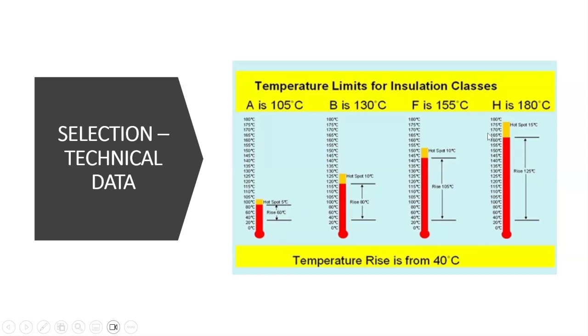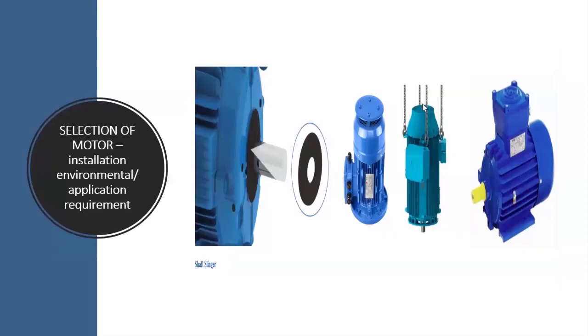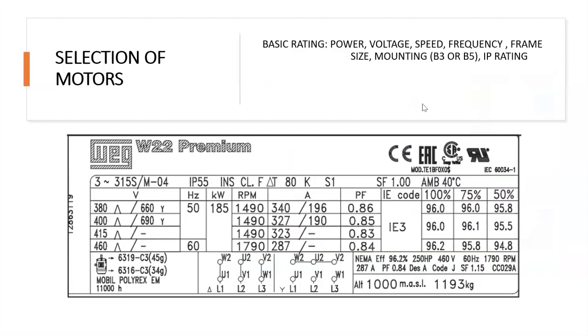Same applies to other insulation class, like say insulation class F. With an ambient temperature of 40, it can rise up to 105, and it has a tolerance of only 10 degrees Celsius. So at 155 degrees Celsius, the motor will fail. So based on your application, if you are going to mount the motor at a hot environment, you specify it and you procure the right motor. Let me go back and show you something on the nameplate data.